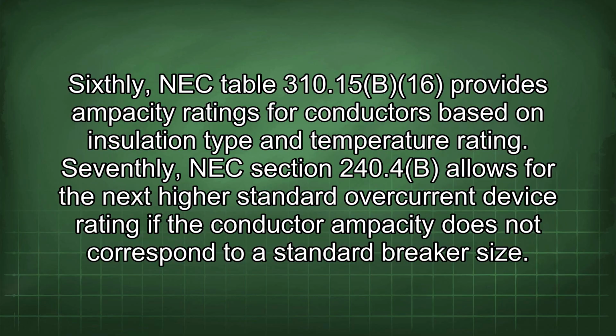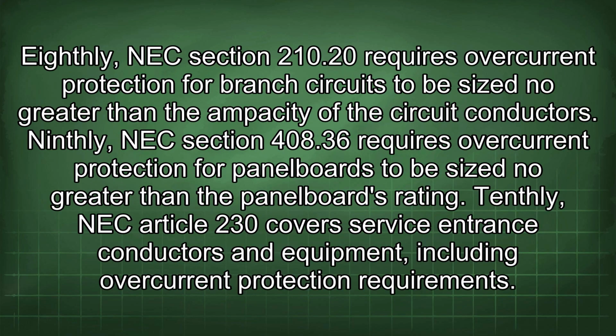Seventhly, NEC Section 240.4(B) allows for the next higher standard overcurrent device rating if the conductor ampacity does not correspond to a standard breaker size. Eighthly, NEC Section 210.20 requires overcurrent protection for branch circuits to be sized no greater than the ampacity of the circuit conductors. Ninthly, NEC Section 408.36 requires overcurrent protection for panelboards to be sized no greater than the panelboard's rating. Tenthly, NEC Article 230 covers service entrance conductors and equipment, including overcurrent protection requirements.